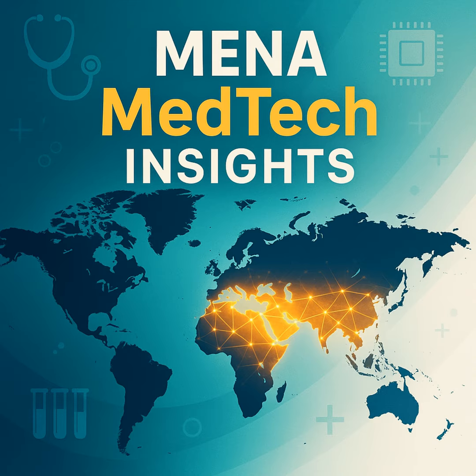However, if you add a feature and claim it can detect atrial fibrillation or monitor blood oxygen levels to manage a respiratory condition, you have fundamentally changed its intended use. It is now unambiguously a medical device, likely a Class A or B low-risk device, and requires a medical device marketing authorization, or MDMA, from the SFDA. This means you need a technical file, quality management system evidence, and an authorized representative in the kingdom.